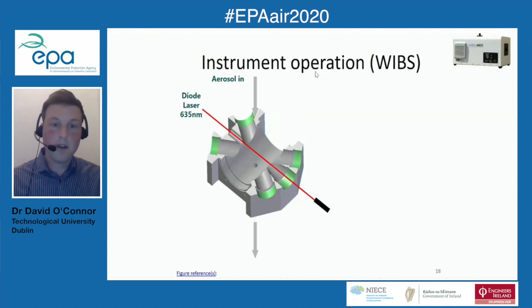It's then hit by a xenon flash lamp at 280 nanometers, and its fluorescence is interrogated between 300 and 410, which is the FL1 channel, and 420 and 650, which is the FL2 channel. If it fluoresces in those areas, they're named FL1 or A-type particles, or FL2 or B-type particles. Then a second xenon flash lamp at 370 nanometers shoots the particle, and we get fluorescence between 420 and 650 again, and these particles are known as FL3 or C-type particles.